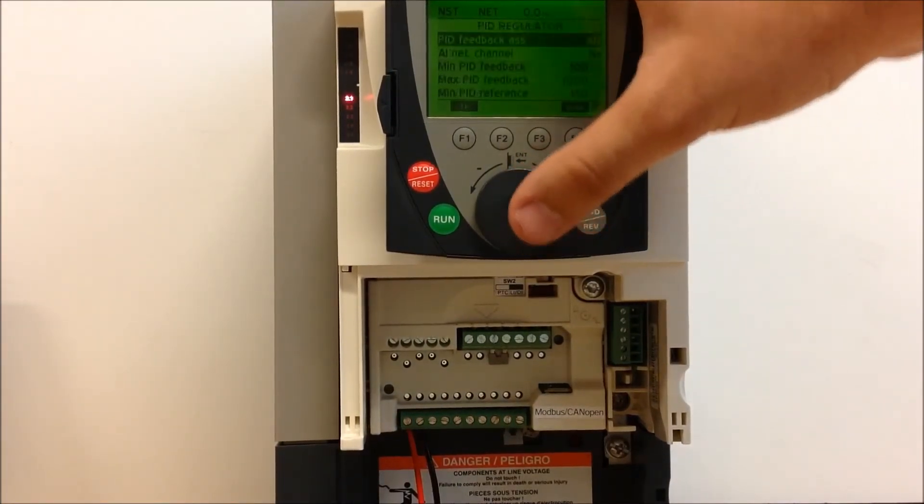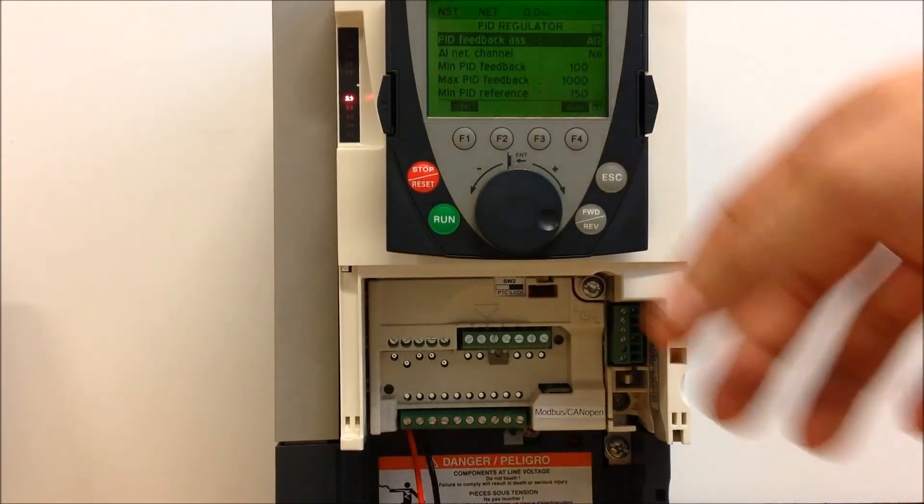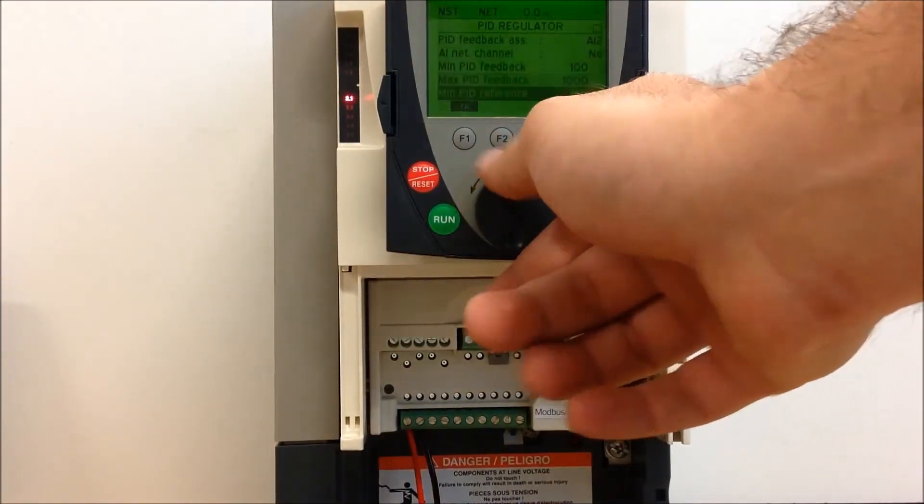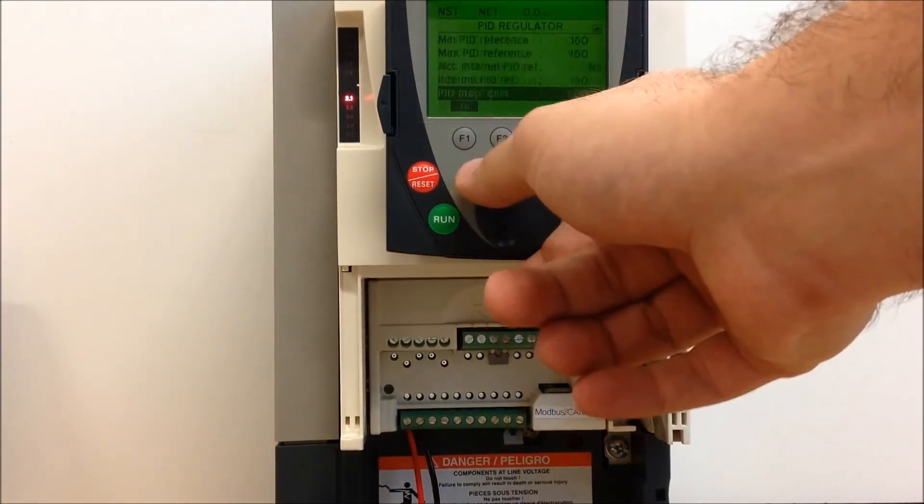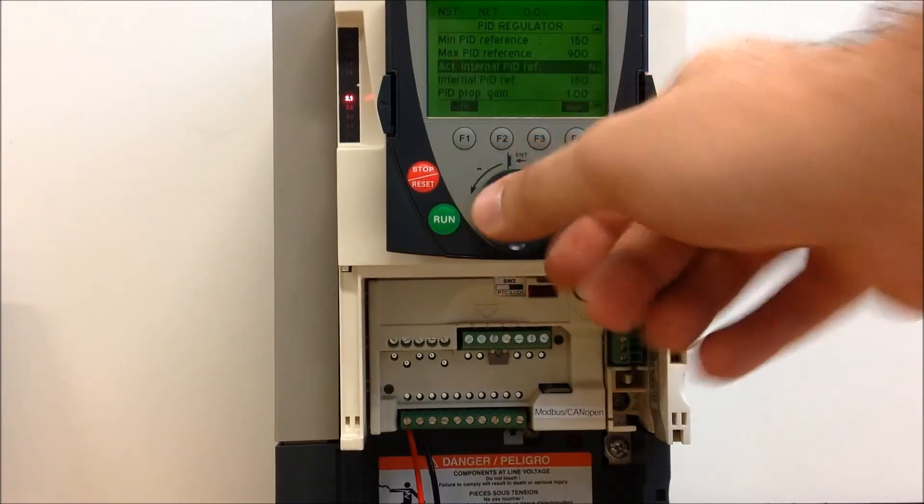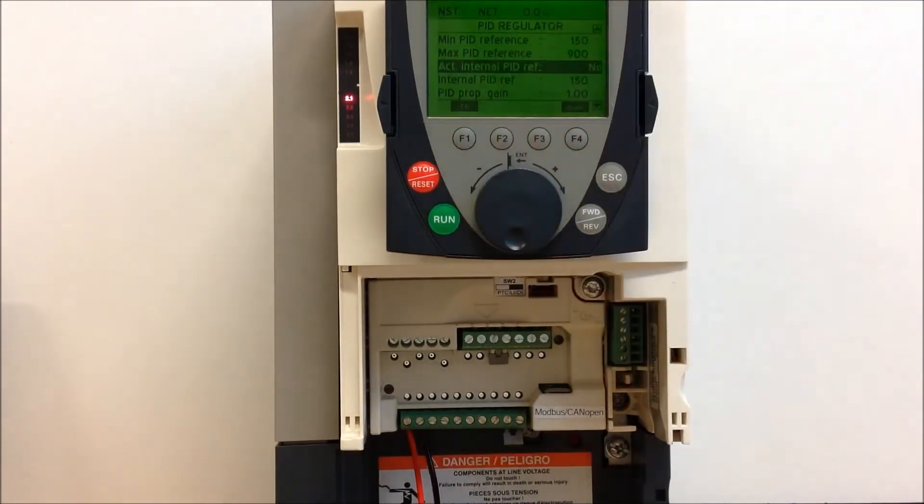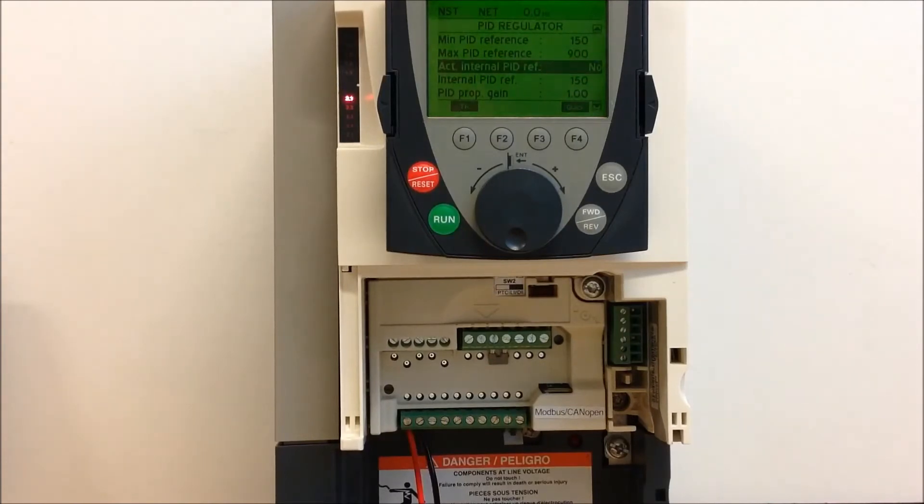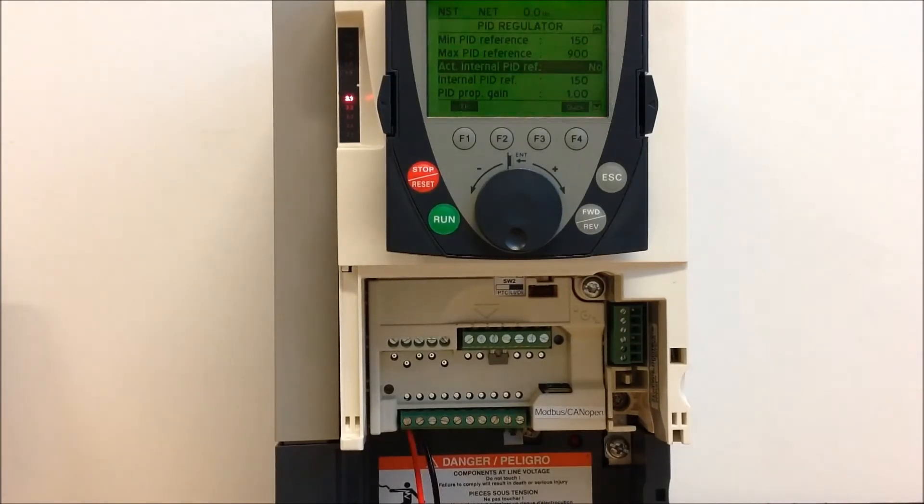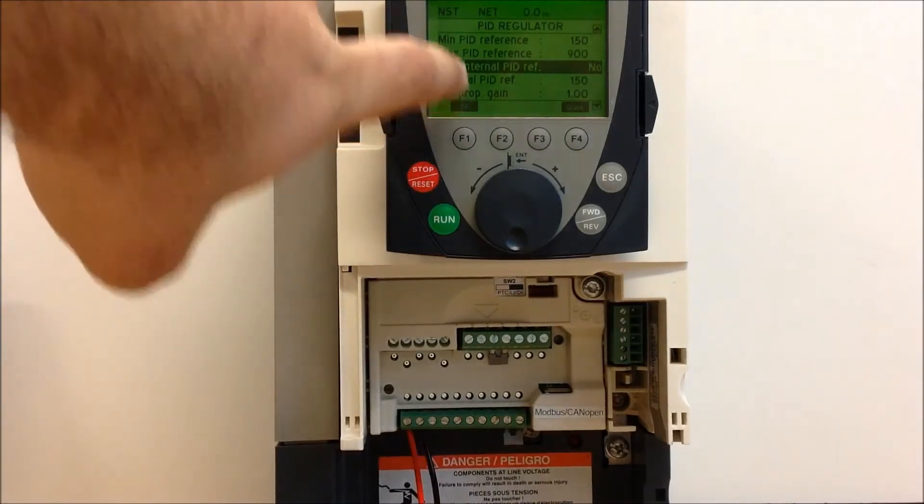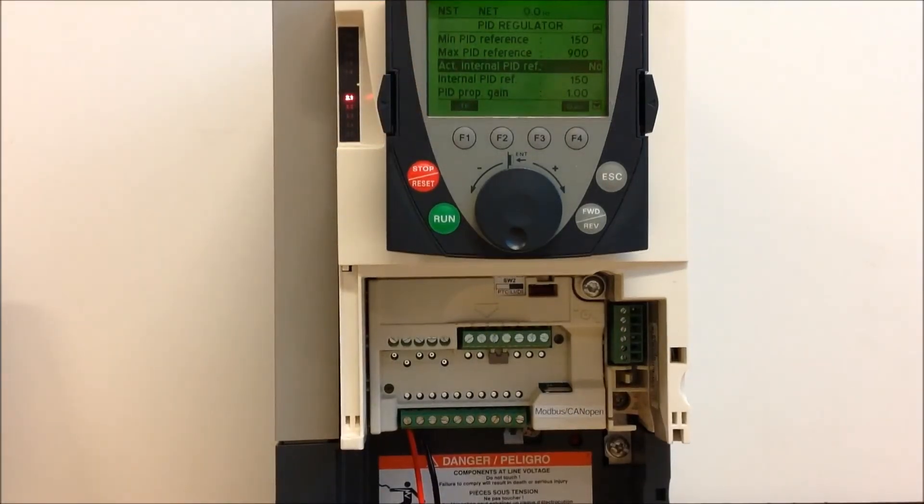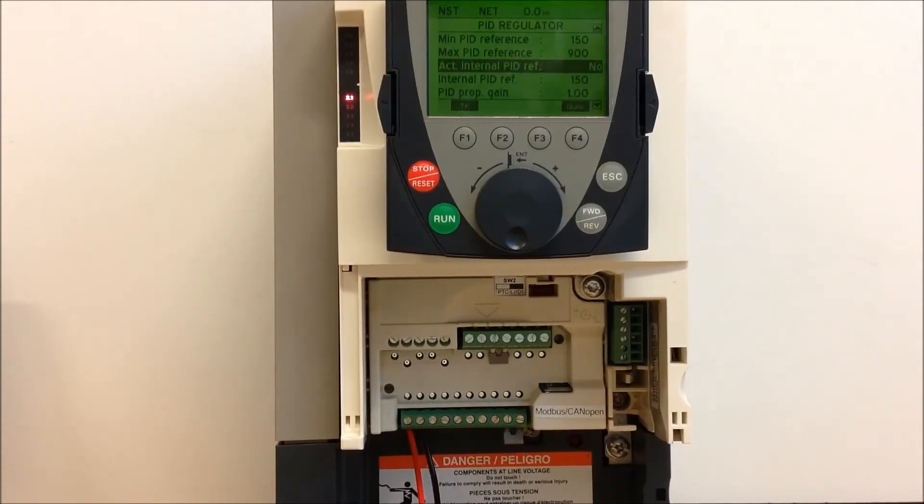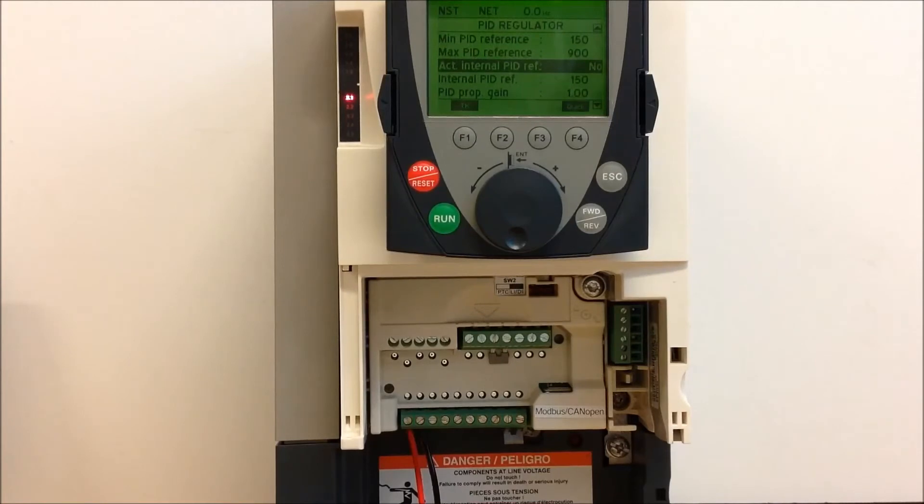Okay, so once you're in your PID regulator, the parameter that you want to make sure is set to no is this one: ACT internal PID ref. So normally you have this turned off, and if you do want to turn it on, then you can actually set an internal PID reference as one single value, and it will stay that way unless you come back in here and change that value from something to something else.